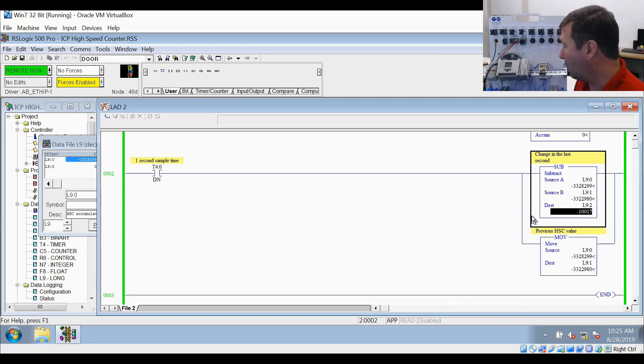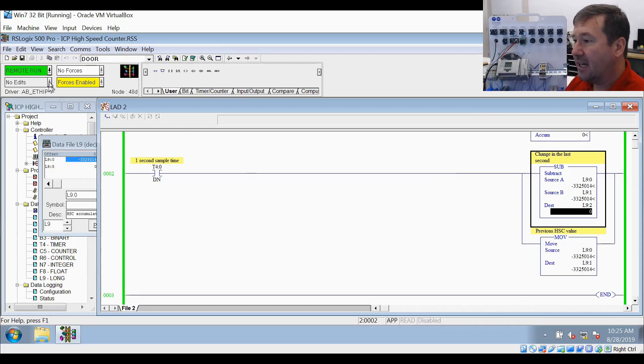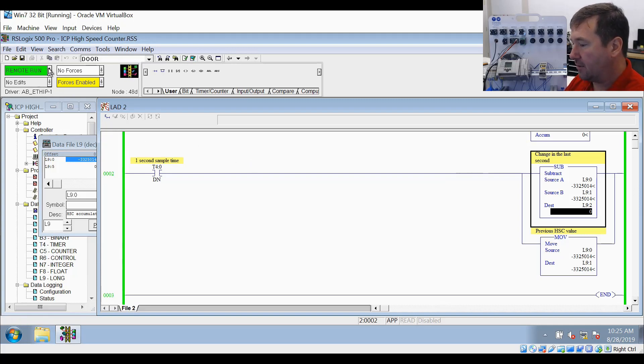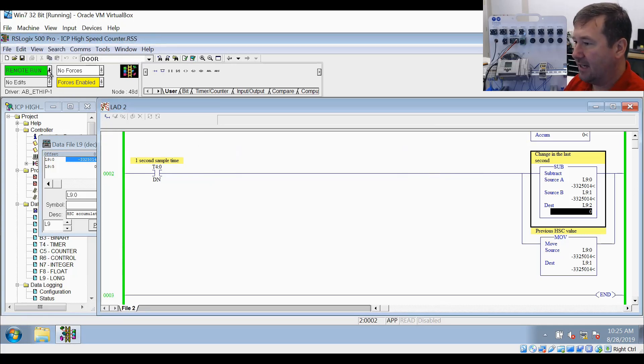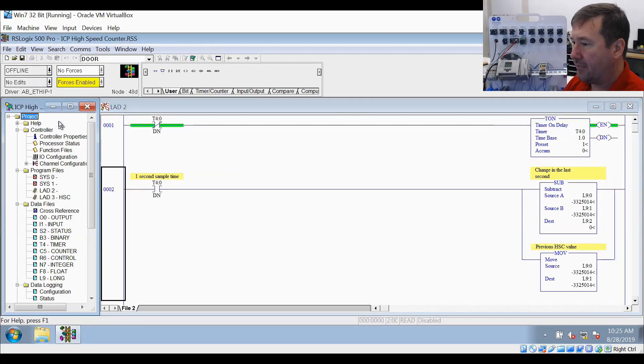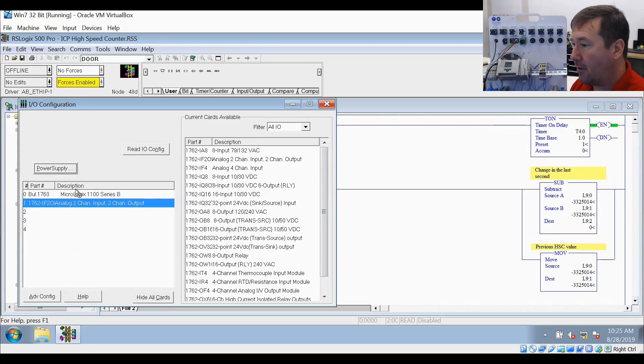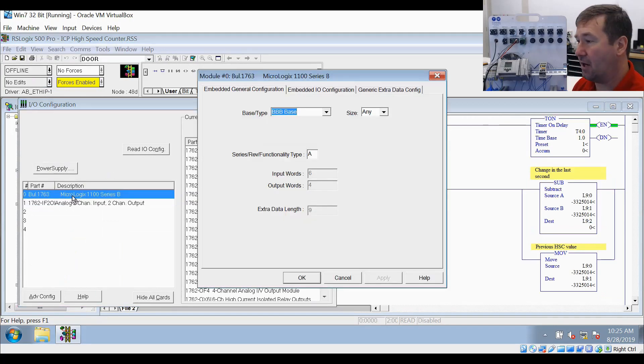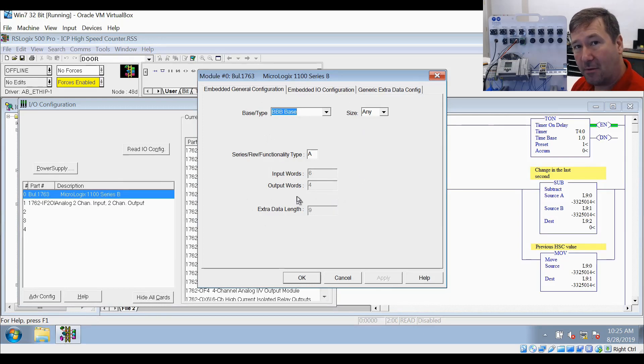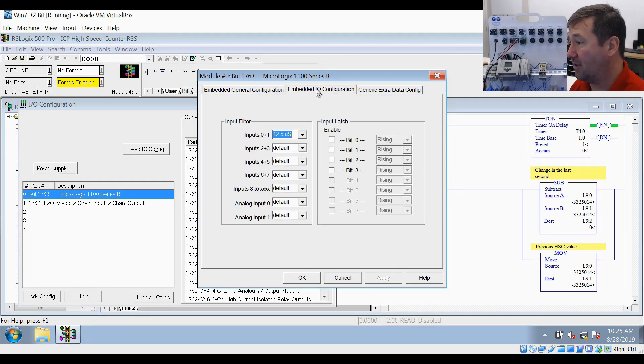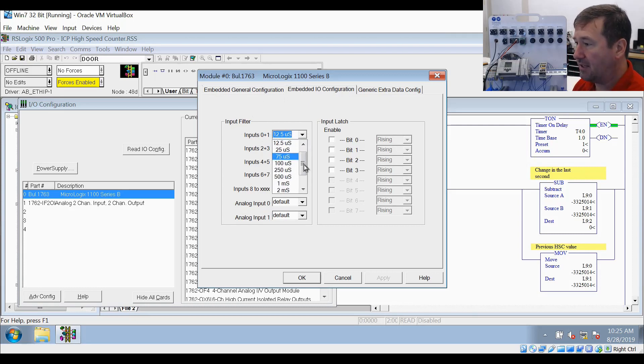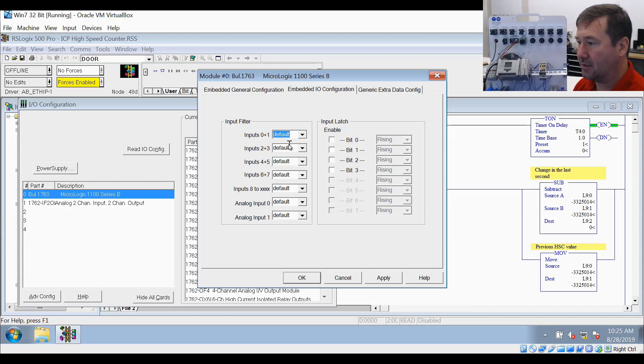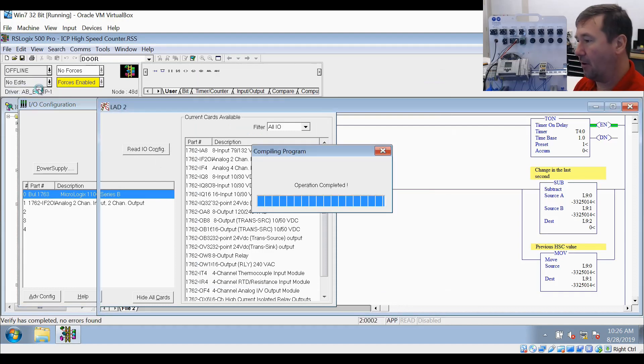Now what we're going to do is stop this and set it back to 10 hertz for our next test. I'm going to go offline, save this program just as it is, and then go to our I/O configuration. We're going to double-click slot zero. This is something you almost never have to go to except for this high-speed counter configuration - that's why it's missed so often. Right here, I've already lowered these input filters to their lowest level, so what I'm going to do is put these back at their default. We'll hit apply and download this program.